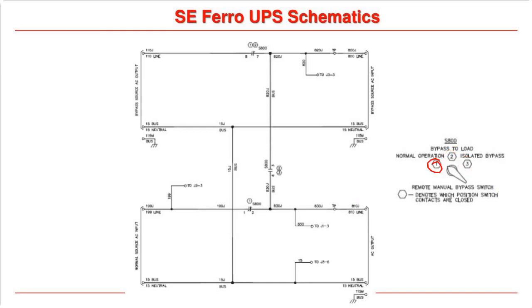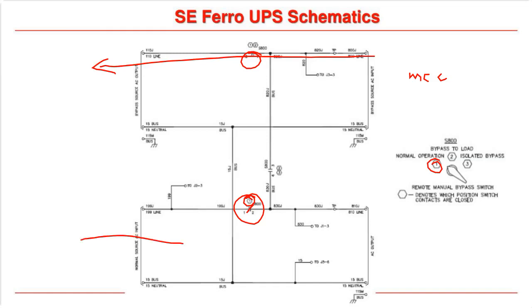Position 1. Okay. This contact here has a 1 next to it, so that is going to be closed when we are in normal operation. This one here has a number 1 next to it, so that is going to be closed. So remember I said this is from your MCC. Bypass supply is going to go that way into your UPS, and then your UPS is going to choose the inverter source and go out this way through that contact there, out to our load circuits. This does not have a number 1 next to it, so that will remain open.